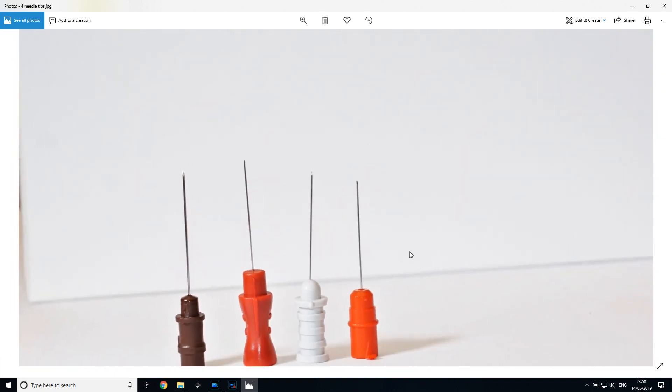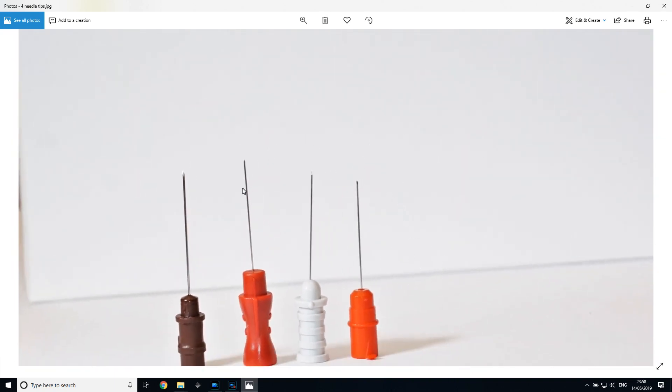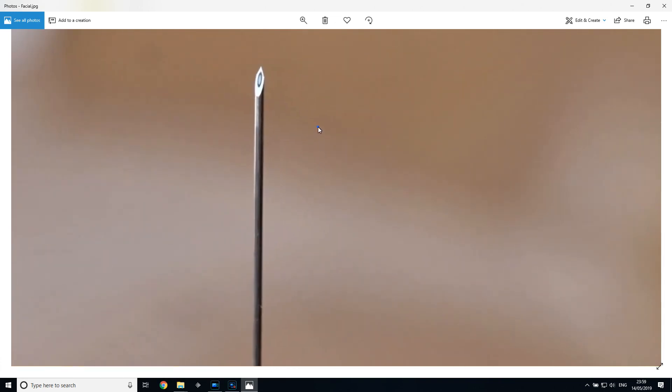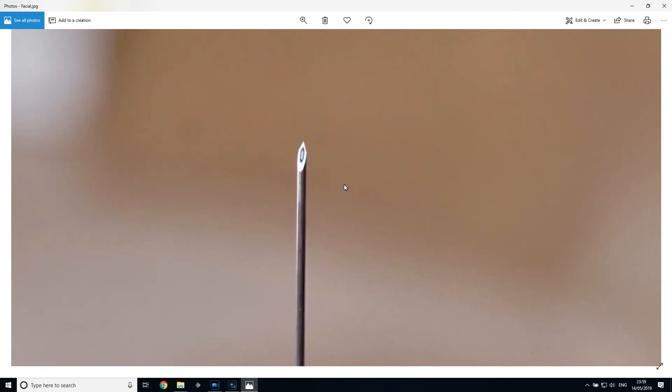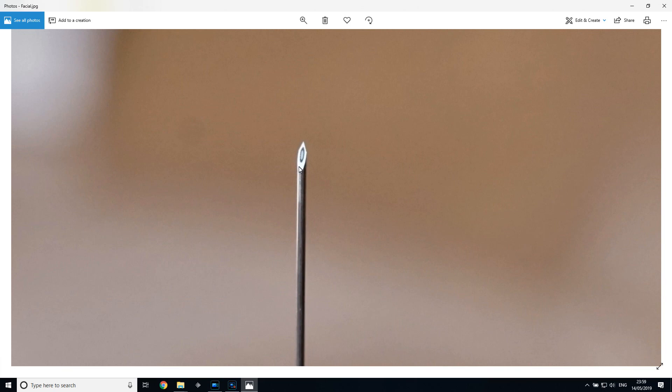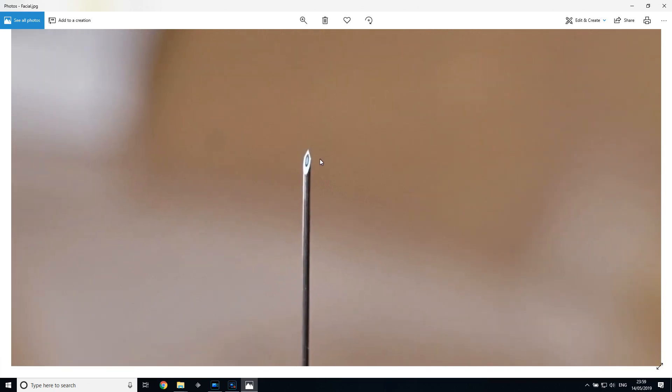So those are the three different facial needle tips, and those are in comparison to the true single fiber EMG needle. The other interesting thing I thought I'd just show you is if I was just taking away the white background and get a bit more contrast here. This is the Tecca point that I was talking about. So here you can see very clearly now, this is the diamond shaped tip of that, and then it's more oval teardrop shape in its inferior segment. So that's that needle tip in more detail.